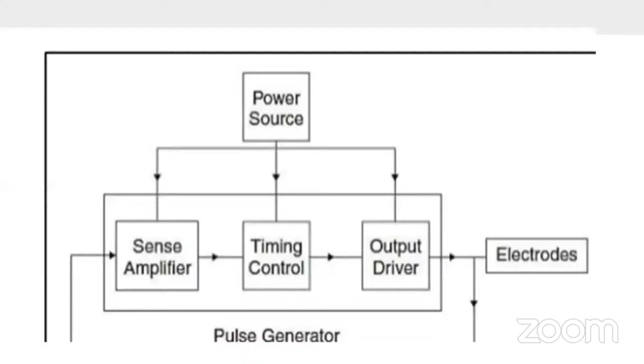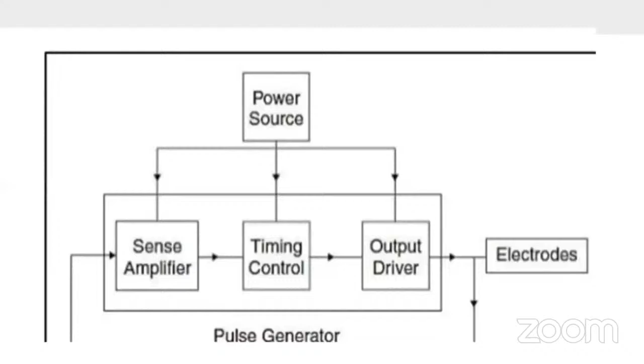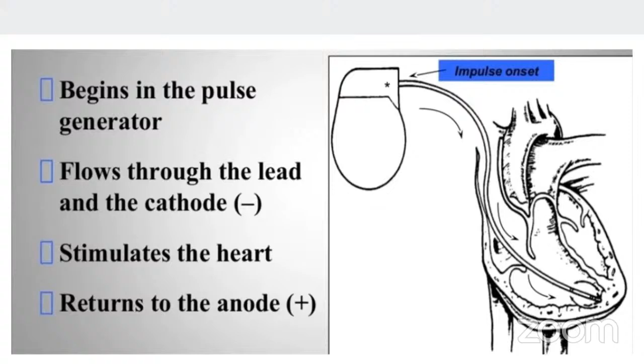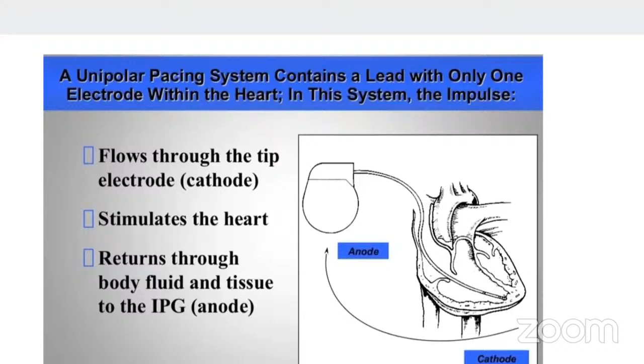And the battery, which is lithium. This is a circuit of the pulse generator: power source, sensing amplifier, timing control, output driver, and electrodes, which relay information back to the pulse generator and vice versa. Once the impulse is started, it begins in the pulse generator, flows through the lead and the cathode, the negative terminal. It stimulates the heart and returns to where it originated through the anode, the positive terminal. A unipolar pacing system contains a lead with only one electrode within the heart. In this system, the impulse flows through the tip of the electrode, which is the cathode, stimulates the heart, and returns through the body fluid and tissue to the internal pulse generator, which is the anode.